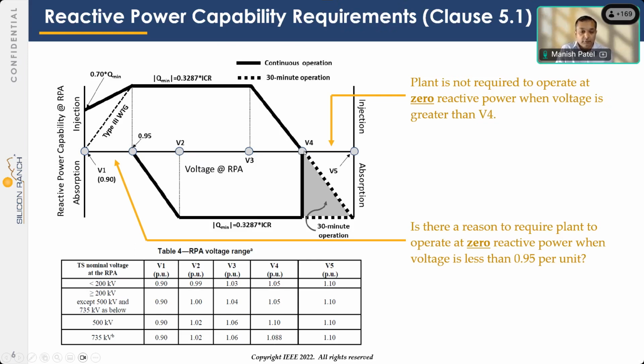So when the voltage is fairly high on the system, there is no need for the plant to operate at 0 reactive power output. When the voltage is high, practically you would like that plant to absorb reactive power from the system, help reduce the voltage on the system, right? So that's why you see this dashed line that goes from V4 to V5 all the way to 33% requirement. But anyhow, what this means is when the voltage is high, we don't need the plant to be capable to operate at 0 reactive power output.